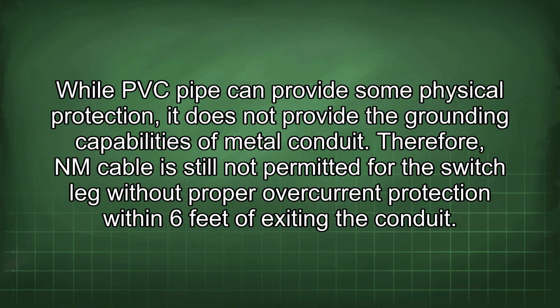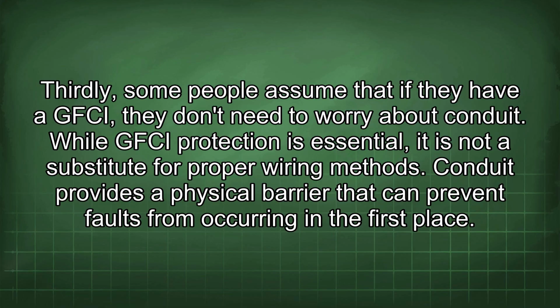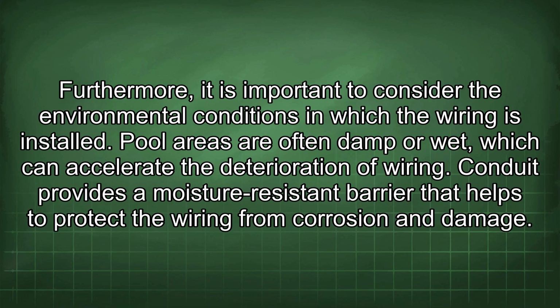Thirdly, some people assume that if they have a GFCI, they don't need to worry about conduit. While GFCI protection is essential, it is not a substitute for proper wiring methods. Conduit provides a physical barrier that can prevent faults from occurring in the first place. Furthermore, it is important to consider the environmental conditions in which the wiring is installed. Pool areas are often damp or wet, which can accelerate the deterioration of wiring. Conduit provides a moisture-resistant barrier that helps to protect the wiring from corrosion and damage.